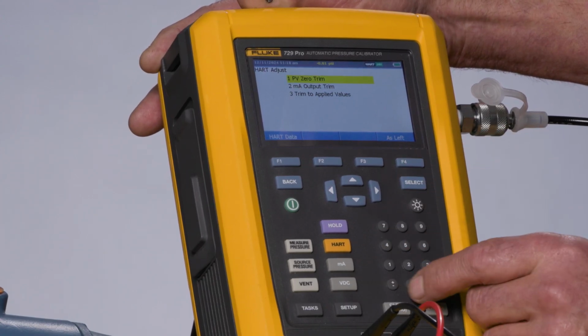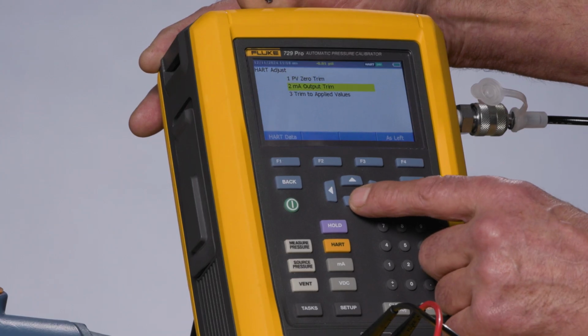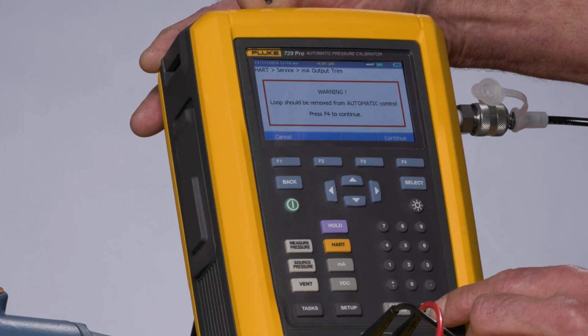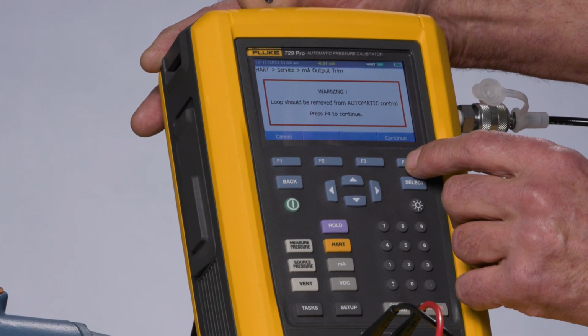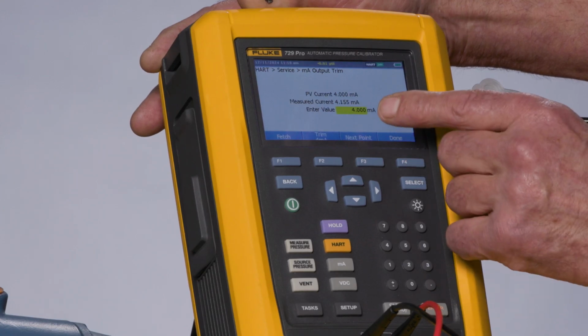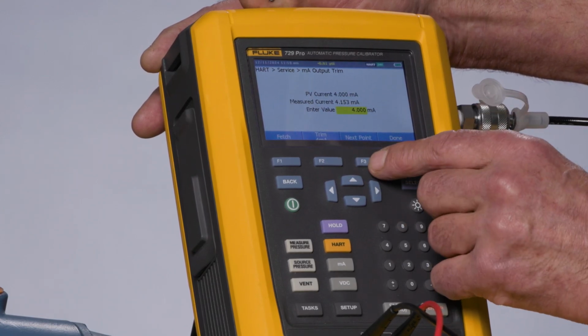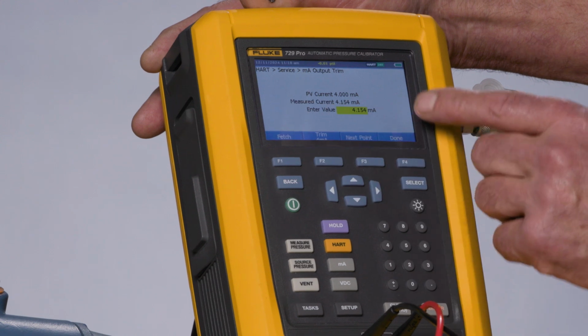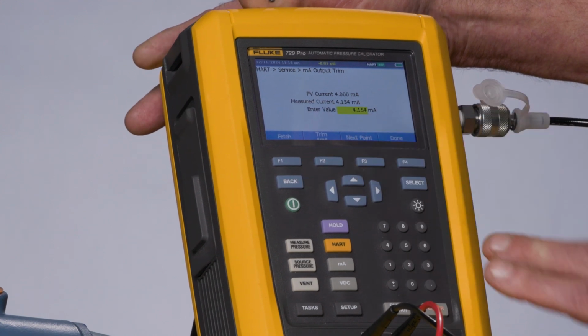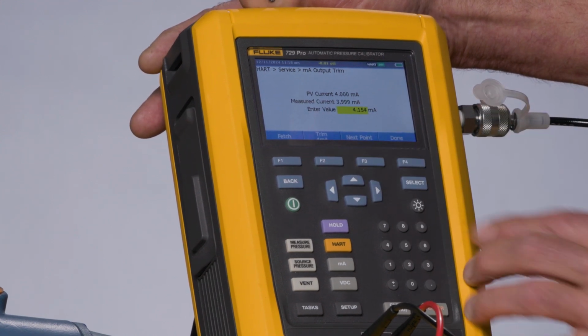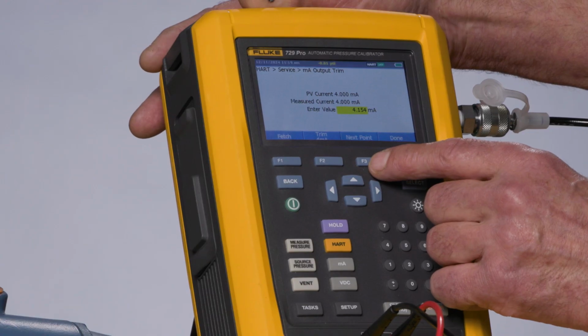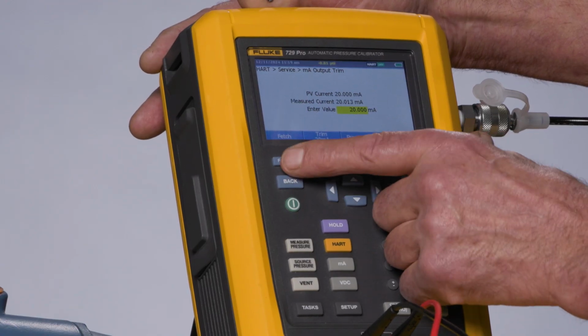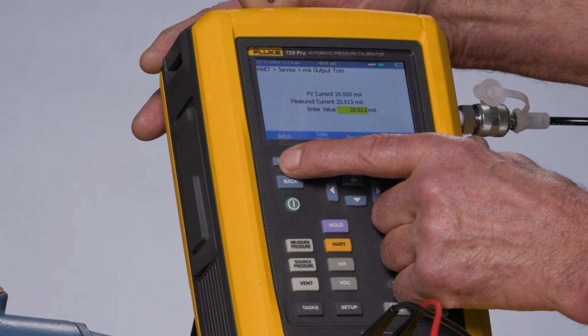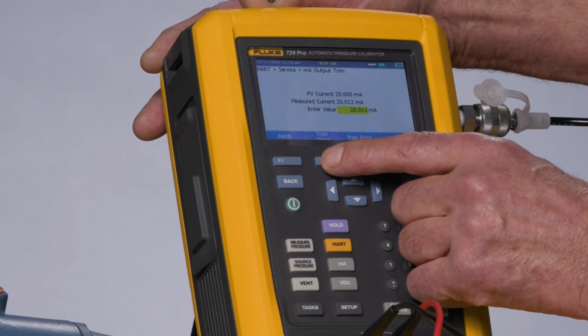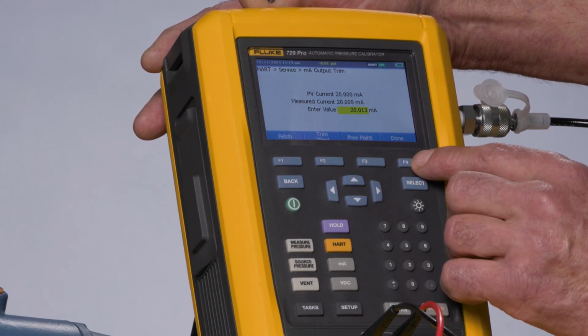And next I would do the milliamps trim. Continue. So first I would fetch the value that's being measured and then trim to make the adjustment for 4 milliamps. And then I would go to the next point. I would fetch the 20 milliamp value being measured and I would perform that adjustment. And then select Done.